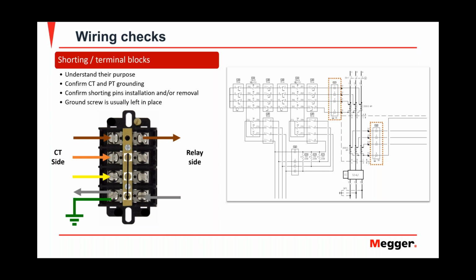So as you go through the sequence, be cognizant of what's happening. I've seen some sites where the electricians share the neutrals, and even though there is no voltage, usually you don't see much voltage in here, but if they share the neutral, you could have current flowing through there if they're sharing the neutral with other circuits. So keep that in mind. So you take your pins, you go through the procedure, and the last one in, and the last one out, I'm sorry, it's the one grounding it. Or leave it in. My practice is just leave that last one in so you know that it's there for the next guy, for the next time.